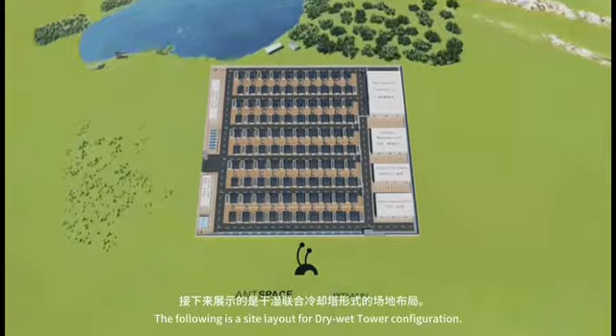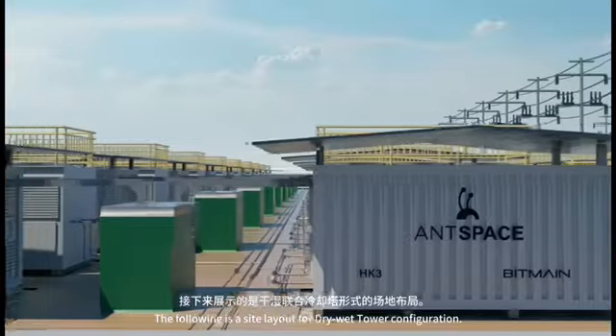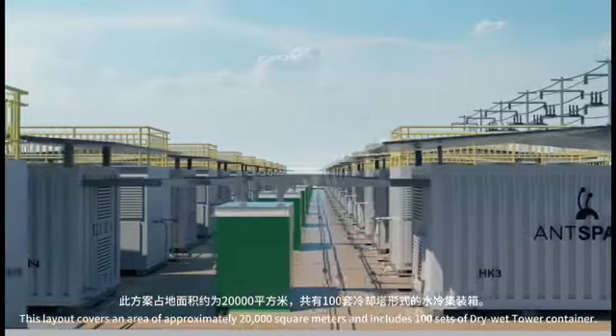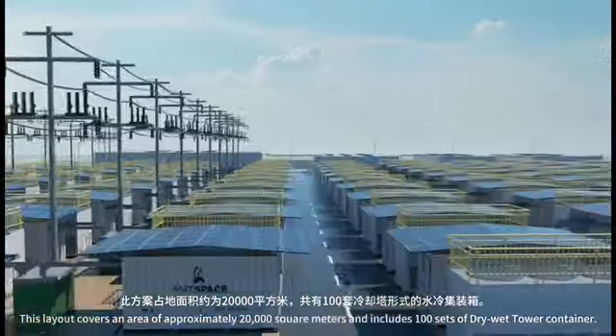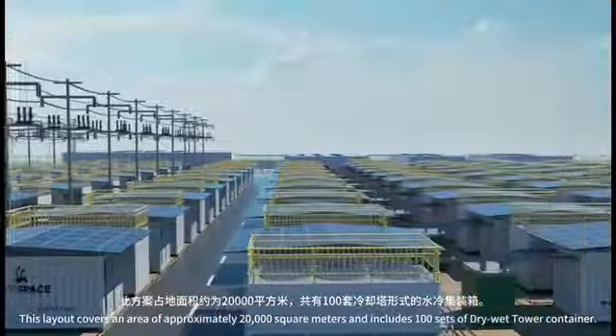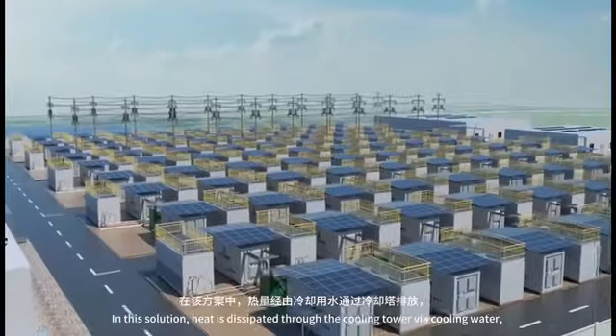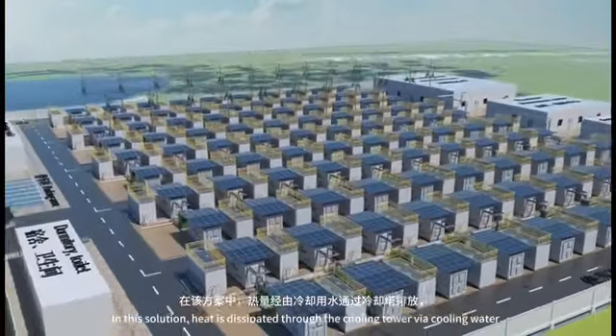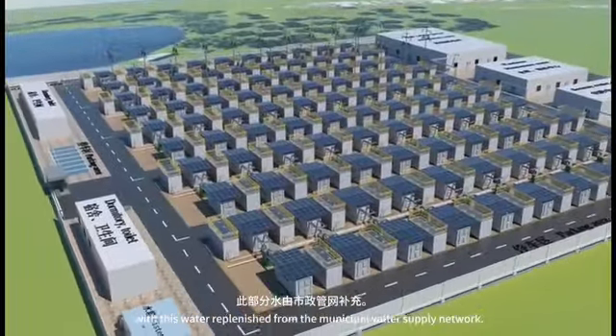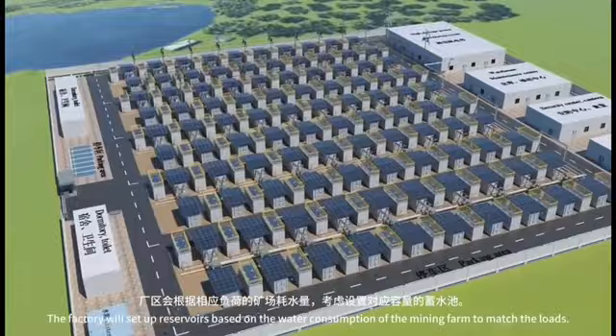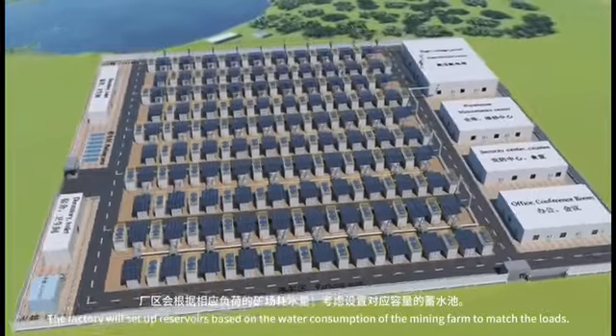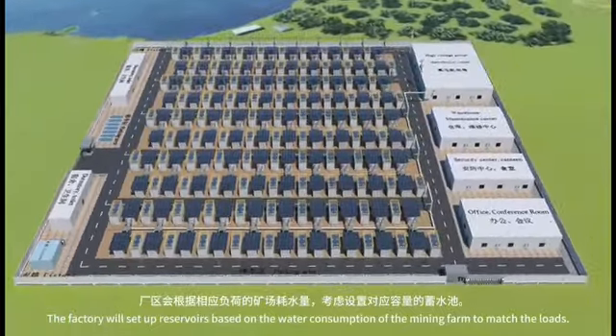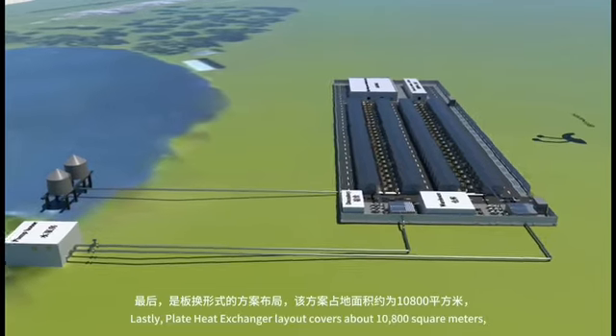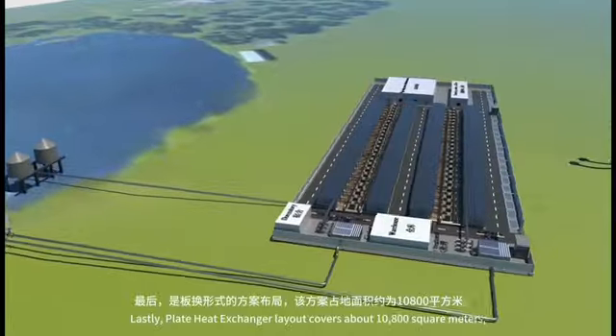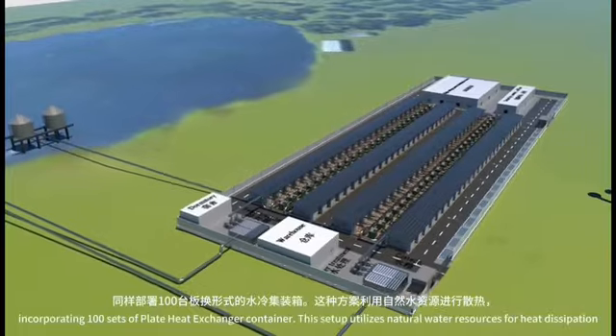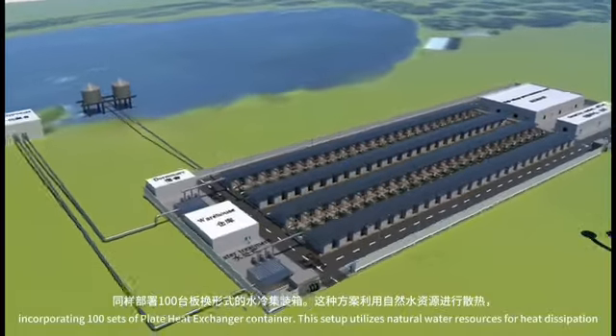The following is a site layout for the dry-wet tower configuration. This layout covers an area of approximately 20,000 square meters and includes 100 sets of dry-wet tower container. In this solution, heat is dissipated through the cooling tower via cooling water, with this water replenished from the municipal water supply network. The factory will set up reservoirs based on the water consumption of the mining farm to match the loads. Lastly, the plate heat exchanger layout covers about 10,800 square meters, incorporating 100 sets of plate heat exchanger container.